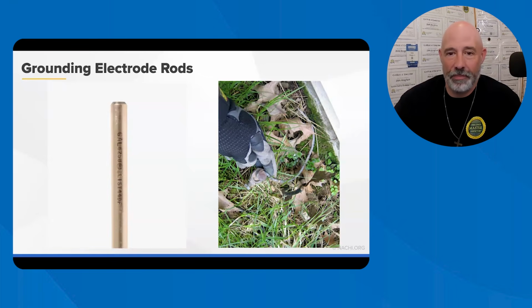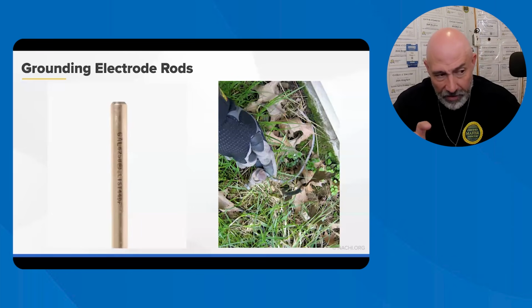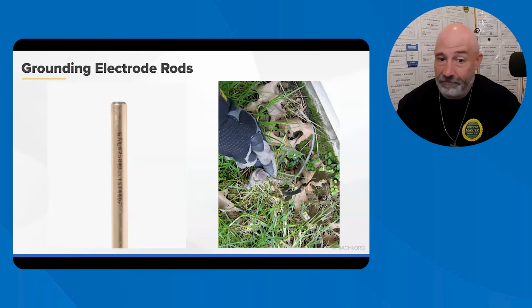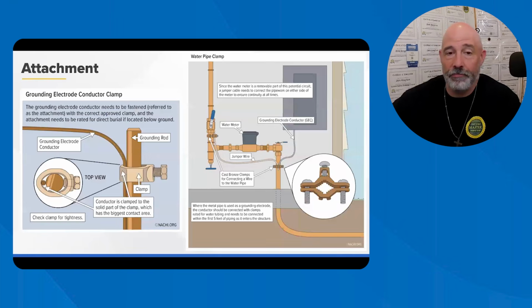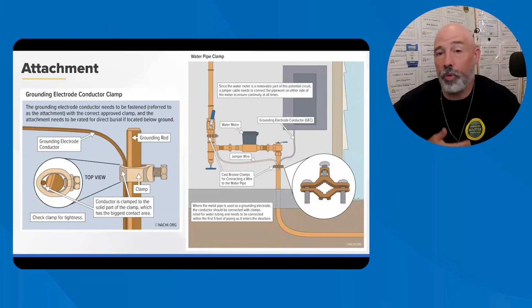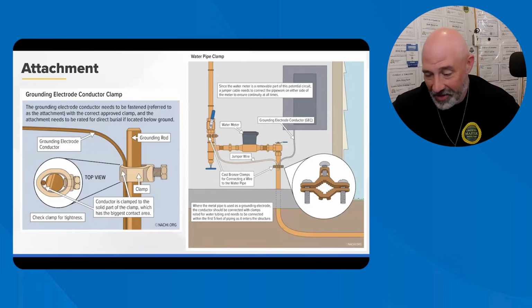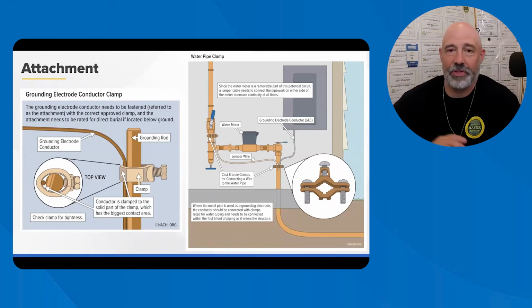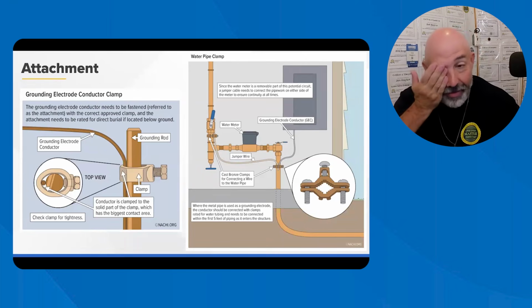Ground rods should be corrosion resistant. They should be properly coated or galvanized. As inspectors, a grounding rod sticking out of the ground is a defect and should be reported. Now, I know if it's like 2 to 3 inches off the ground, typically that's what they're saying here. Grounding electrode connections. The grounding electrode conductor must be secured with an appropriate clamp. I've seen different people use hose clamps. I've seen them put the wire on the wrong side. I've seen just weird stuff. These are acorn clamps. They're commonly installed incorrectly. I've seen it 1,000 times. Like, oh man, who put this on?